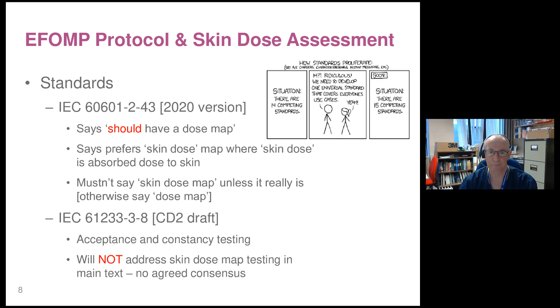Now, there is another IEC standard that I'm on the working group for, and it's quite a task actually, getting everyone to agree on how you should do acceptance and constancy check testing of radiographic and fluoroscopic equipment. This project will not address skin dose map testing in the main text. There's no agreed consensus whether we can get something in an informative annex. I think that's the right terminology. I don't know yet. And we're currently out for the CD2 draft. That's being drafted at the moment. We're hoping to go out to a vote early in the new year, sometime around Easter.